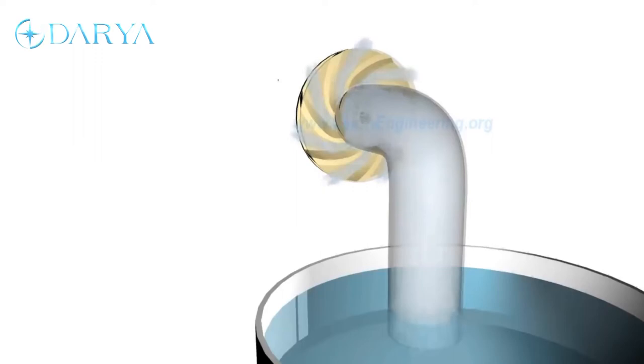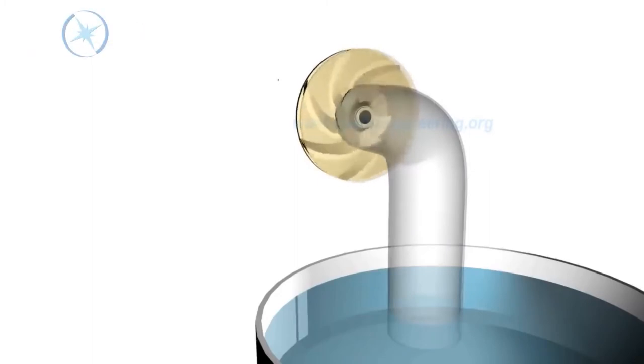This is the reason why priming is important for centrifugal pumps. If no water is present initially, the negative pressure developed by rotating air at eye of impeller will be negligibly small to suck fresh stream of water.